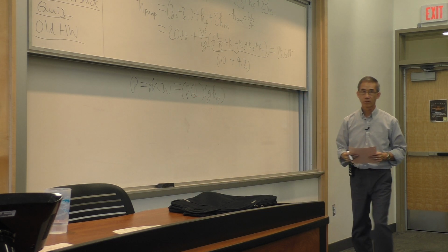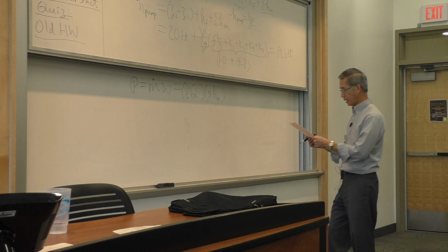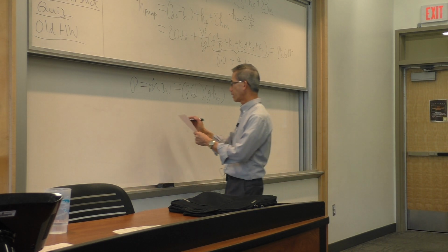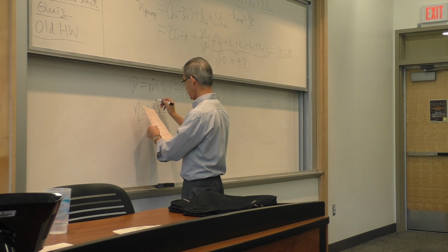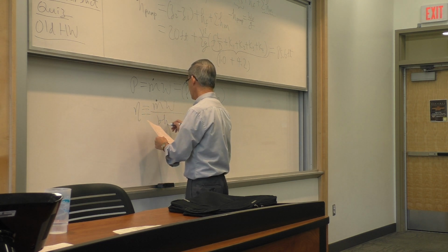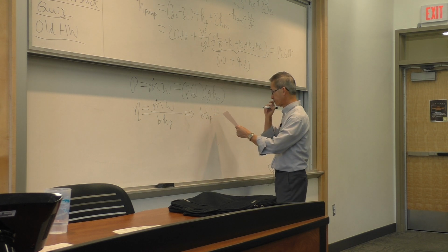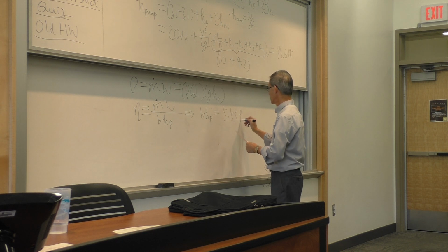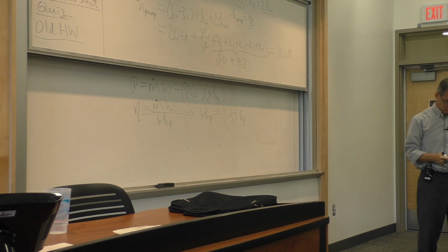M dot, which is now rho Q or rho VA, and the specific work, which is now given equivalently by gravity times the head rise due to the pump. And that will be, when you do all the numbers in horsepower, accounting for the 70% efficiency of the pump, the denominator, the brake horsepower, is what I'm after. And when you go through the numerics, it's about 6 horsepower.